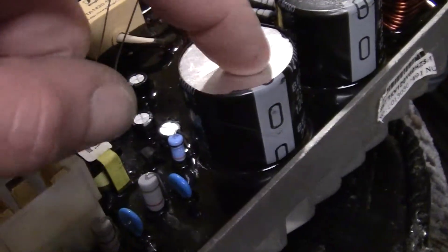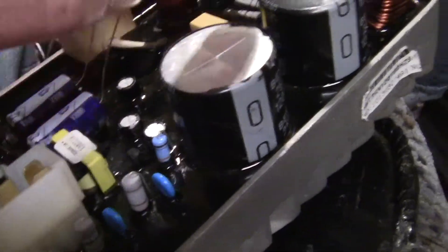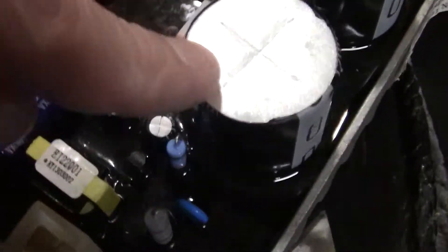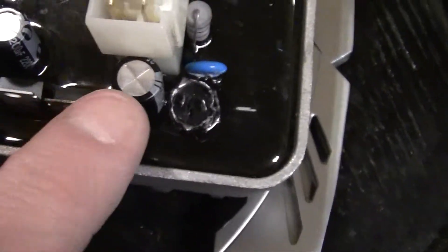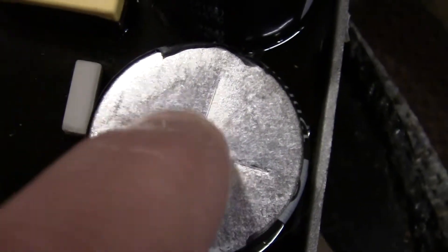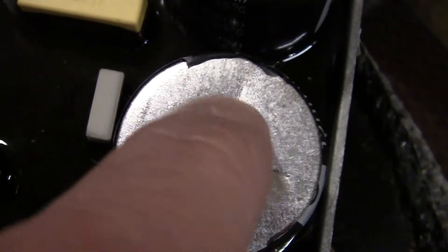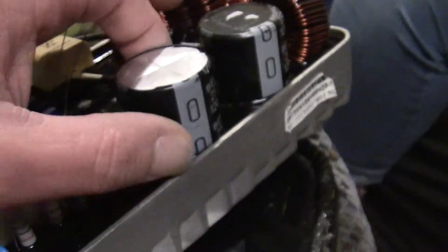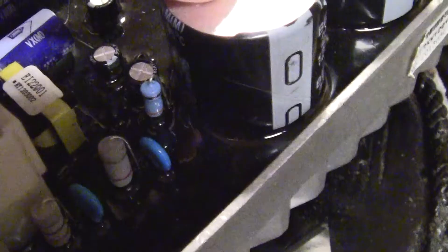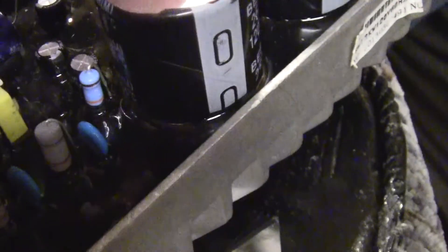Now I did take this cover off this cap. I took it off because most times when these caps blow, like this one here that I took out - that's the leak. 99% of the time they'll blow right out the top. I have seen them bulge on the sides, but if they actually pop you'll see it right in the middle, weeping right there.